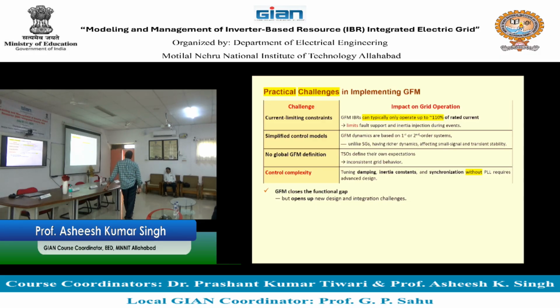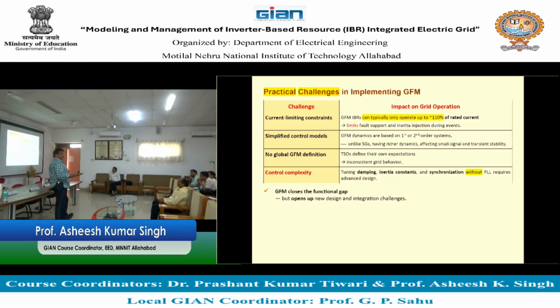Simplified control models. GFM dynamics are mostly based on first and second order systems, right, but practically they are not, right. These control systems or their control models typically have much higher order, and for this they use model order reduction. They bring it to first and second order. Unlike synchronous generators, which have richer dynamics affecting small signal and transient stability, which is not there because of no SG, that is a challenge for them to provide.